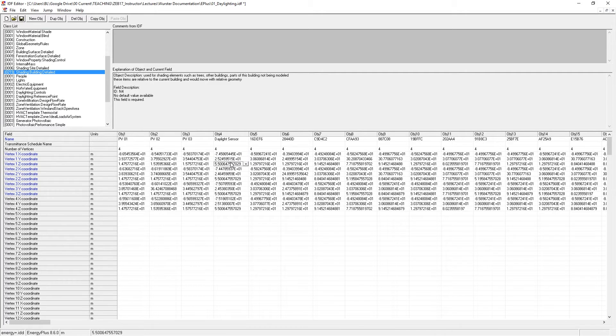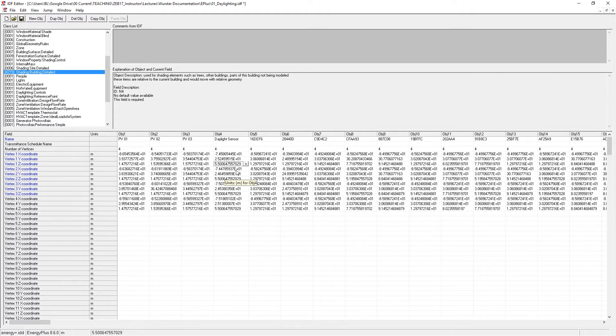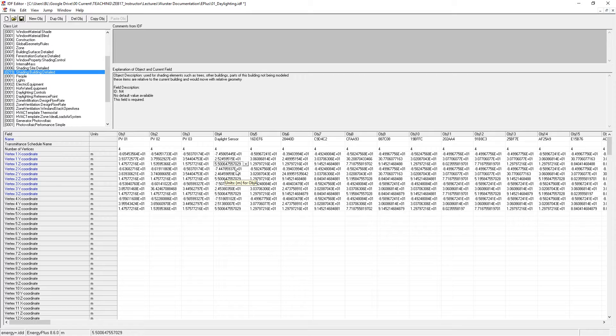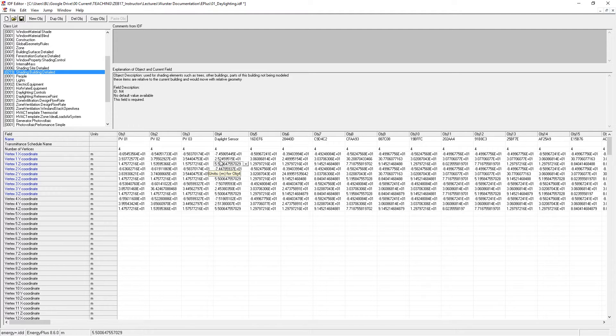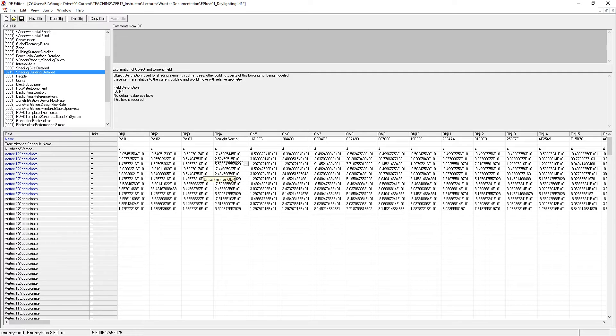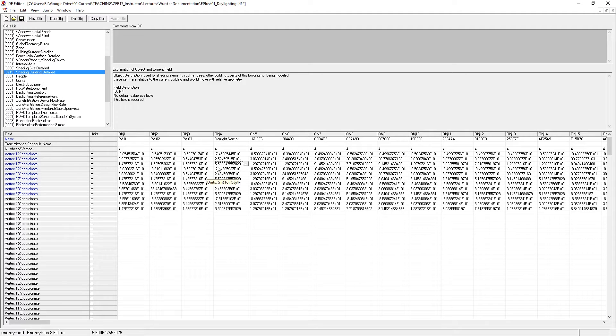That's important when you round. You want to make sure that you're rounding so that the sensor is inside the zone. If the sensor is outside the zone, it will not work because it's not seeing the daylight inside the zone. So in this case, I don't have to worry about rounding my 75 or my 25, but my 5.5 is on the floor of the zone. So I want to make sure that the sensor is just slightly above the zone or above the floor. So I'll record this as 5.51.